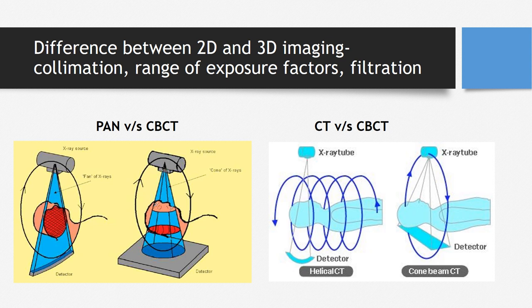There is a difference in collimation, the range of exposure factors, and filtration when comparing a CT scan versus a CBCT. A helical CT has the x-ray tube and detectors move in a helical pattern around the patient's body, exposing a single area multiple times to give a 3D volumetric image. Whereas cone beam CT only exposes a conical-shaped area within the head and neck region.